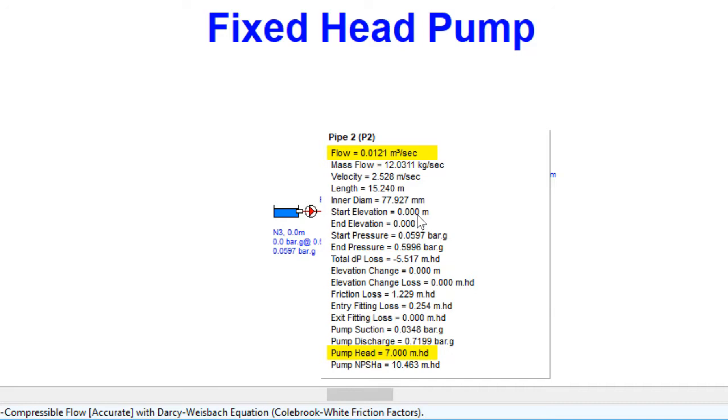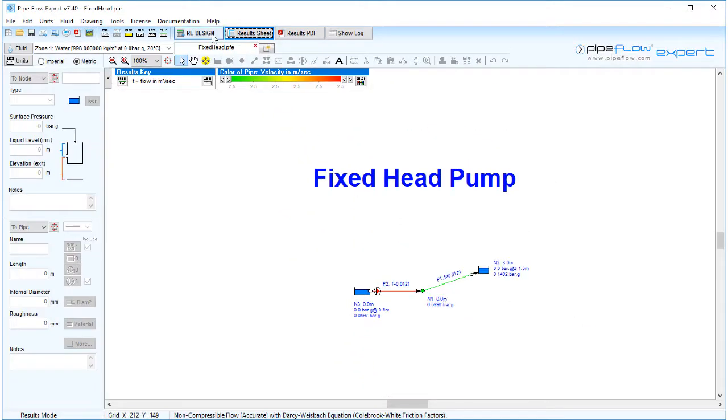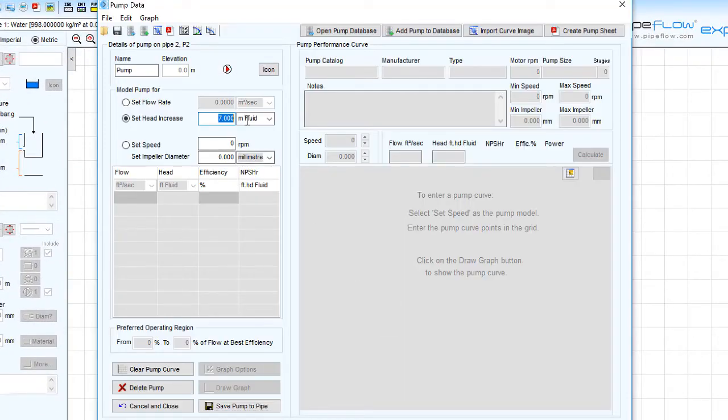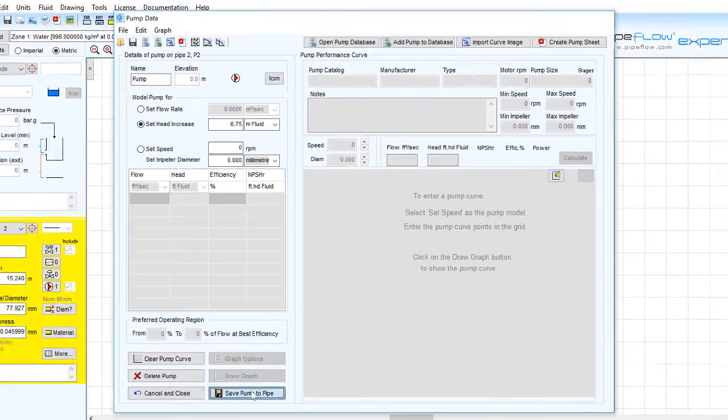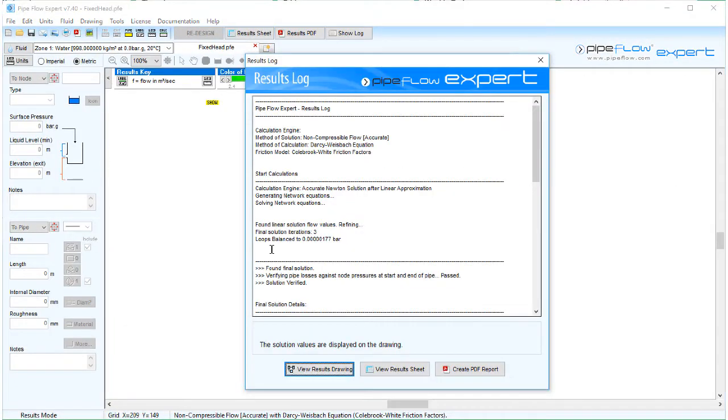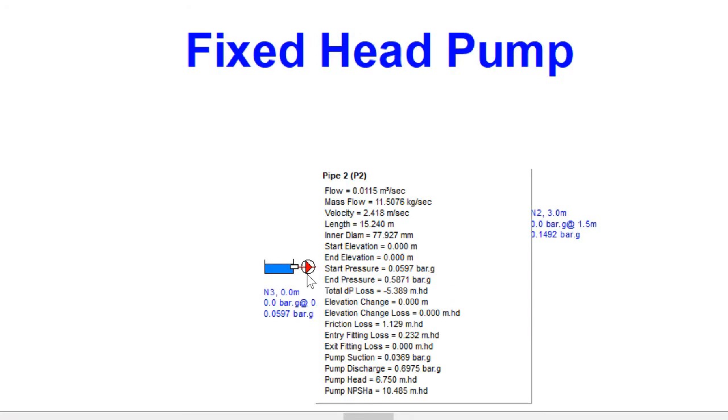By changing the head increase value to 6.75 meters head, we can now see how this affects the flow rate. Our final result is a fixed head pump adding 6.75 meters of head, yielding a flow rate of 0.0115 meters cubed per second.